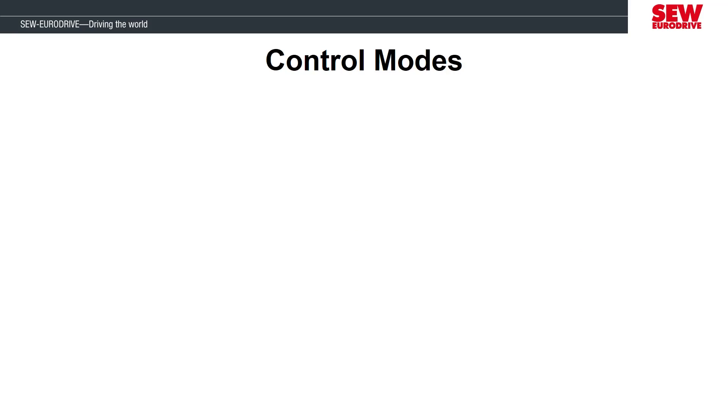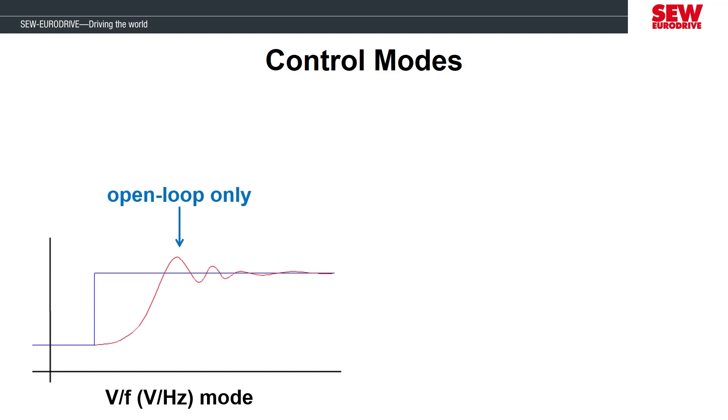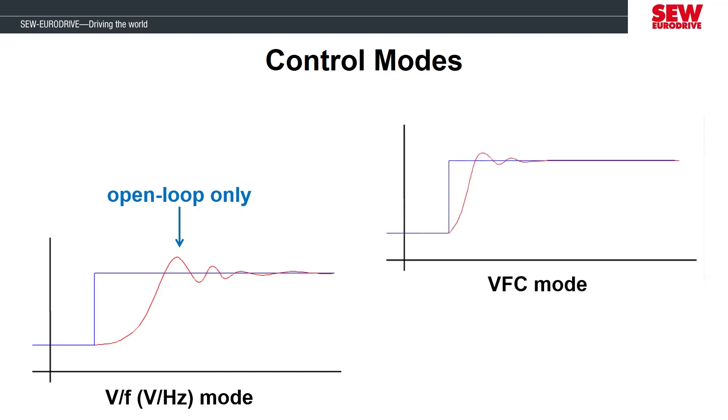The MOVIDRIVE has several different operating modes that can be changed in the motor startup for different applications. In the previous labs, we have been operating our motor in a voltage and frequency mode that is open loop, which means that even though we have an encoder connected to the inverter, we have been ignoring the signal. VF mode is great for a lot of simple applications where precise speed or positioning is not needed, but the MOVIDRIVE is capable of more complex operating modes where speed, positioning, or constant torque is important. In this lab, we are going to change the startup mode from VF mode to VFC mode.